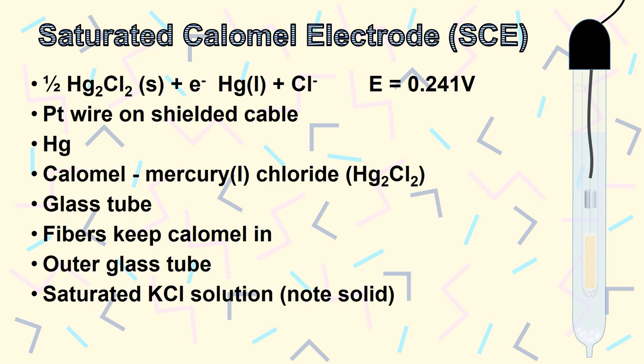A small amount of saturated solution leaks out through a ceramic frit at the bottom. This is how conductivity with the solution is established, while keeping the solid KCl inside the electrode. Note that the vent must be open to allow air into the electrode for that small amount of solution to leak out the bottom.